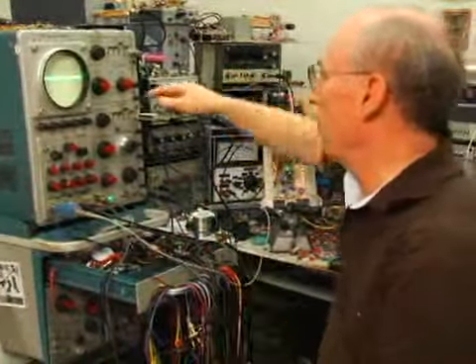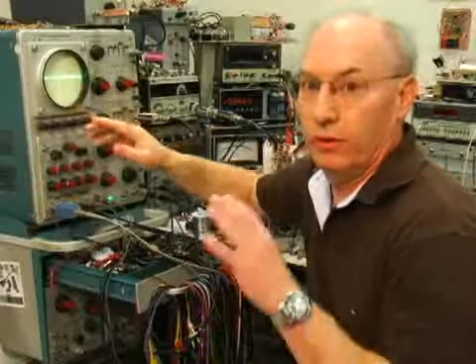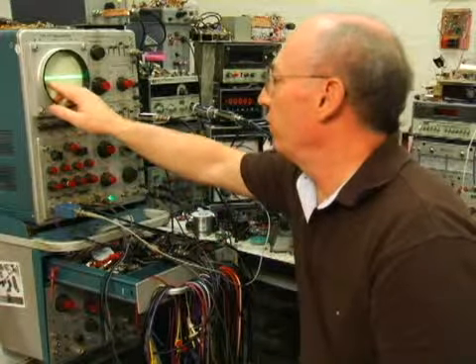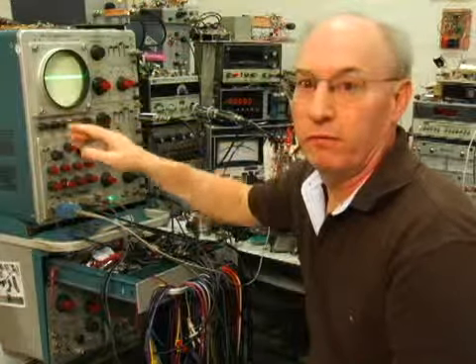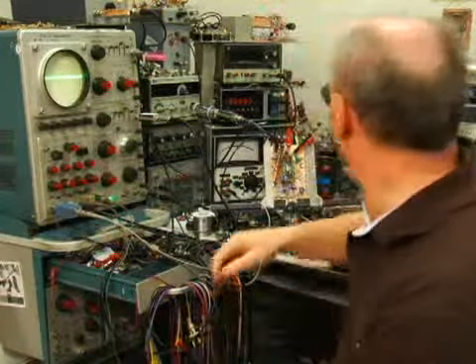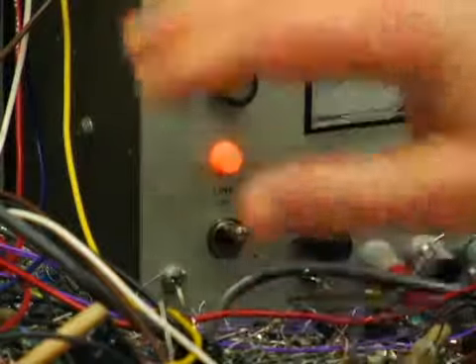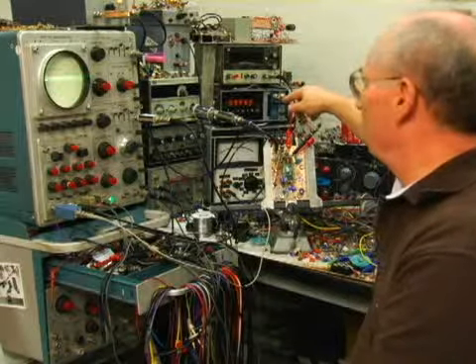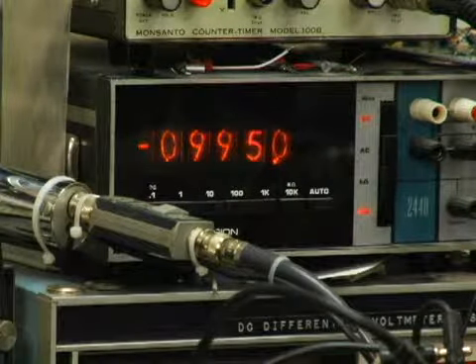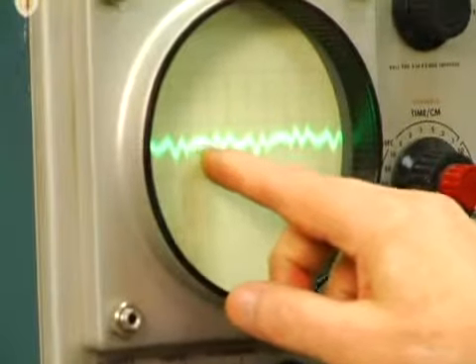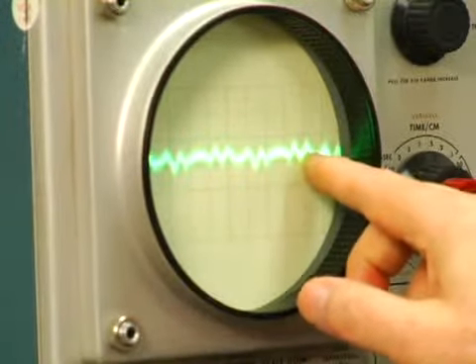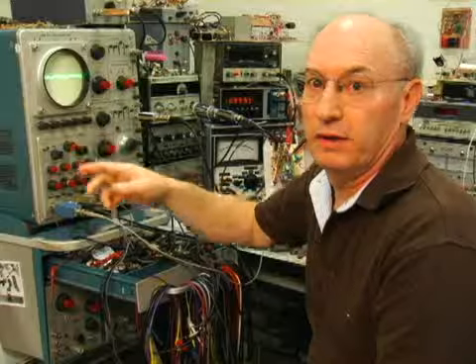Right now the converter's off. I'm measuring my noise floor at quiescence. The noise floor of the test setup is about 100 microvolts peak to peak. Now I'm going to turn the converter on. The voltmeter indicates we're just below minus 1000 volts. And what we've got on the scope at 100 microvolts per division is about 100 microvolts peak to peak of noise, total harmonic content. That means I'm getting about 1 part in 10 million noise on the output of my 1000 volt converter.